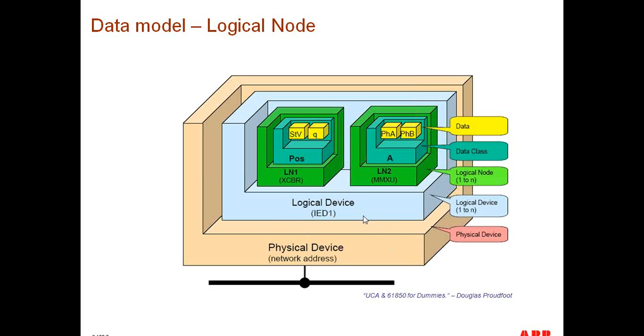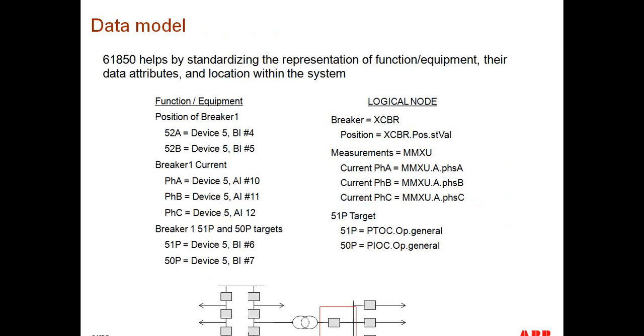And then inside that physical device, we house what's called a logical device. And inside a logical device, you have different logical nodes. And what logical nodes represent, they actually represent functions. So let's say a 51, a 21, a 27, a 59. Well, there's a logical node for each one of those protection functions. For a 21, for example, there's PDIS, which is the logical node for an impedance element. For differential, you have PDIF. So all of these different protection functions, as well as monitoring functions such as metering or breaker control, there are logical nodes that are standardly defined in IEC 61850.